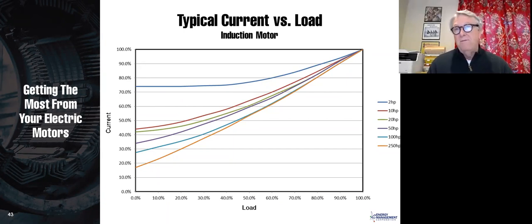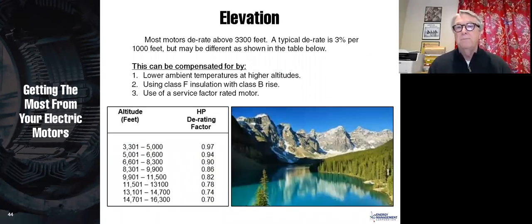And when you reach about 50% load, this isn't accurate to 3 decimal places, but we just want to say that in general, if you measure the current on a motor, you compare it to the full load current, you'll find that the load and the current from 50 to 150%, this only goes to 100%, but from 50 to 150, the current and the load are pretty much proportional.